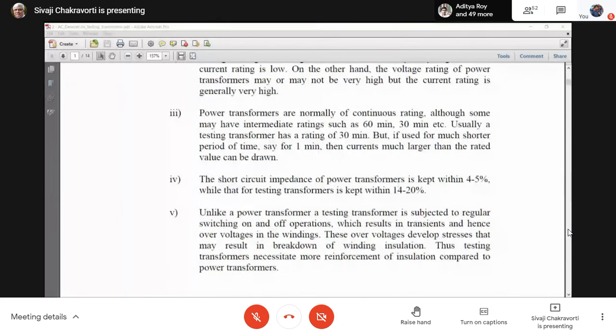Then the third point is, a power transformer is a continuous rating equipment. You know, there are two types of equipment. We call it continuous rating and intermittent rating. Continuous rating means that the equipment can run continuously for 24 hours, 24 into 7, whatever you say. Whereas some equipments just run for a short period of time. For example, a testing transformer. When we do the testing, we switch on, and then it might be used maybe for 15, 20 minutes, 30 minutes for the testing, then switched off. So there is a big difference in what is called the type of loading. One is a continuous load type, the other is called the intermittent load type. And the design, etc., that whole thing changes.